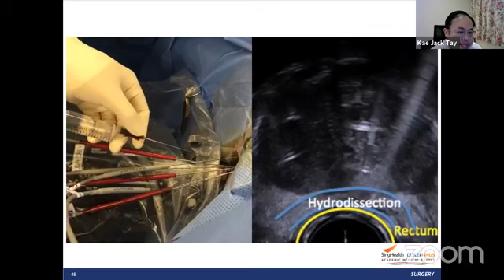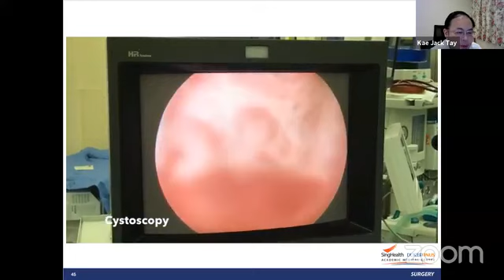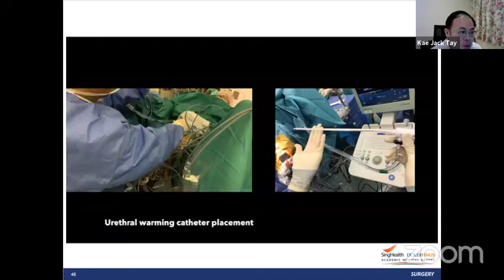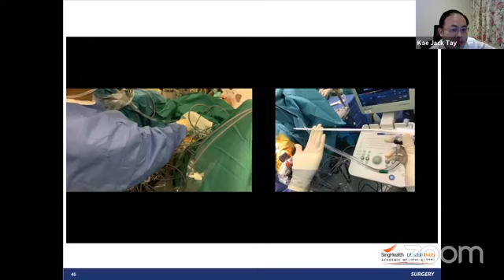Yeah, so here, because that medial one was near the rectum, we did some hydrodissection, basically injected some saline there. It's temporary and goes away after a short while. Before we start, we do a cystoscopy, make sure that there were no probes traversing the urethra. Then we put in a urethral warming catheter. So this cycles warm water through the urethra in this catheter to make sure the urethra remains safe. That also means that there's about a 5 mm zone where you don't get a kill around the urethra. So that's important to know because if there's a cancer that's very near the urethra, probably not suitable for cryotherapy.